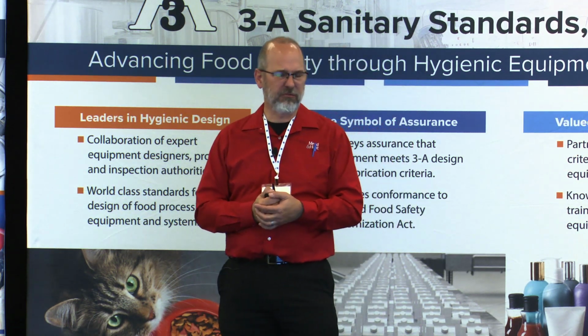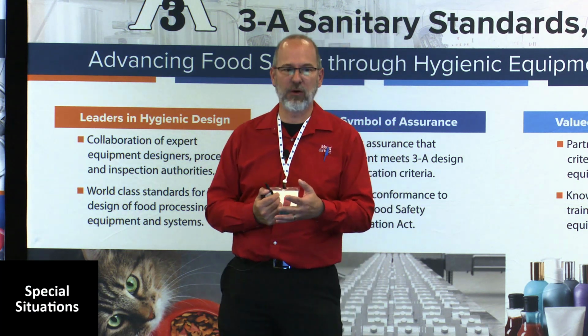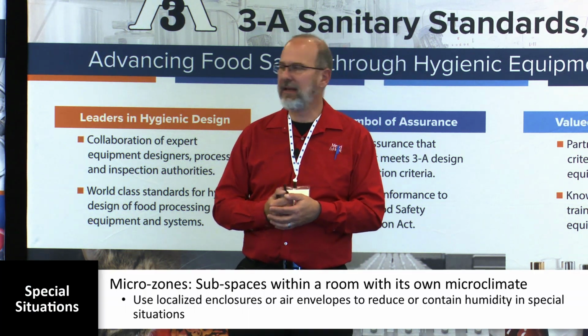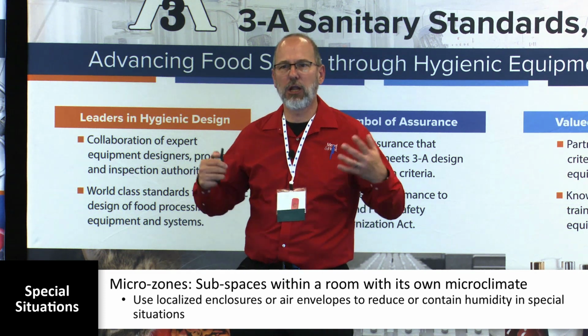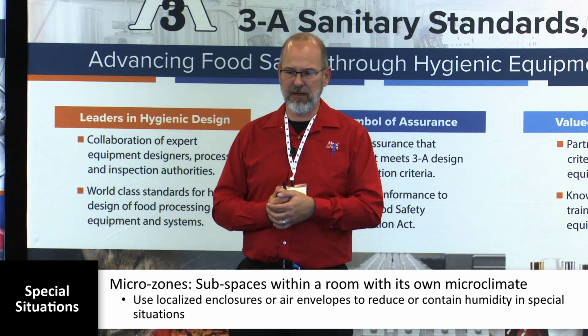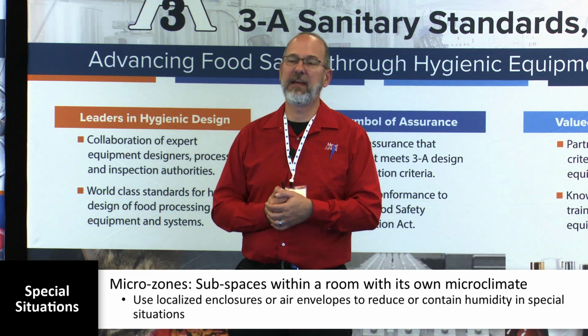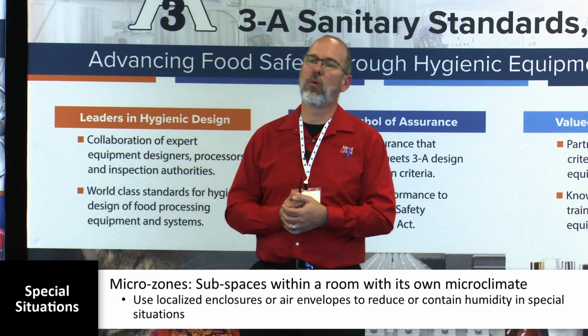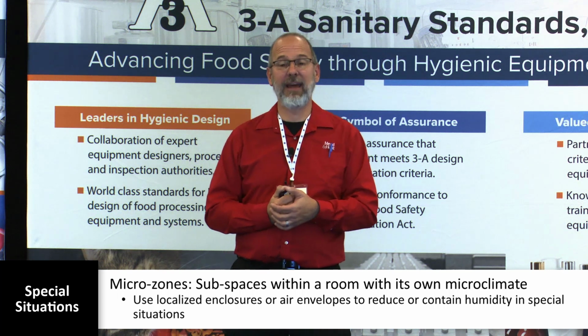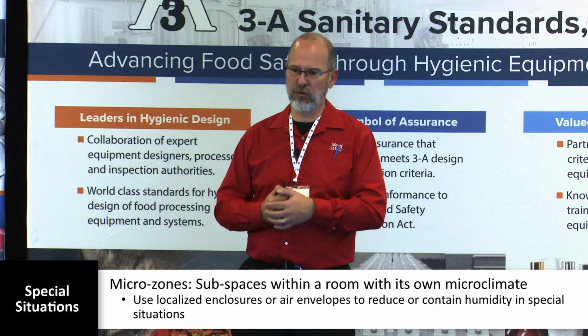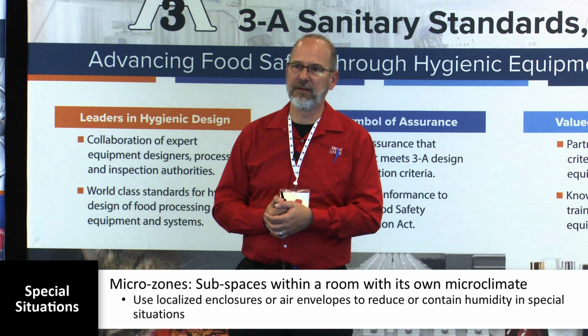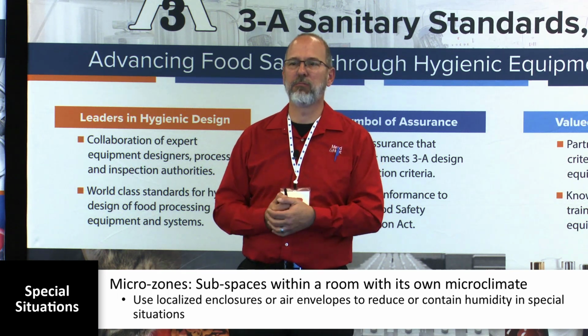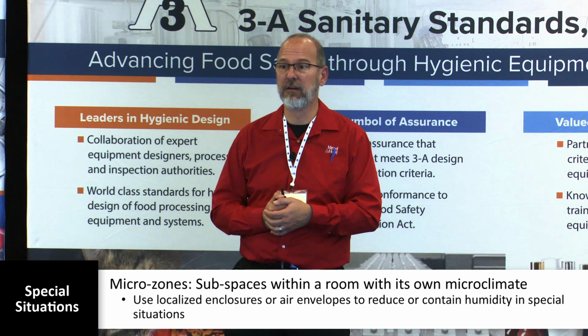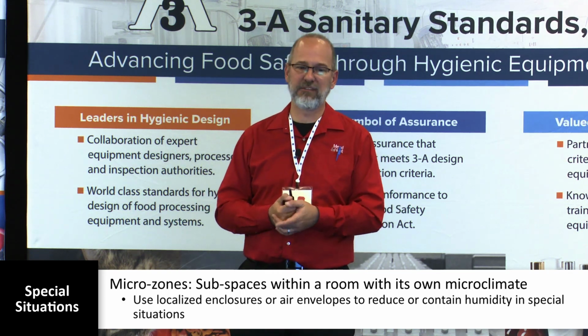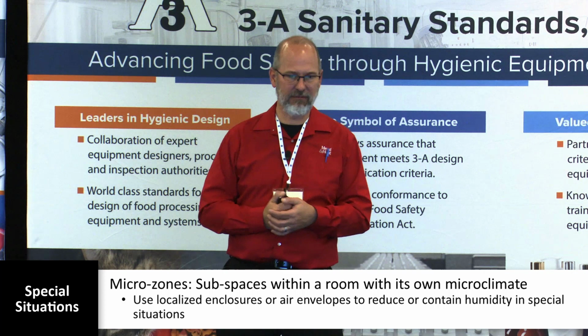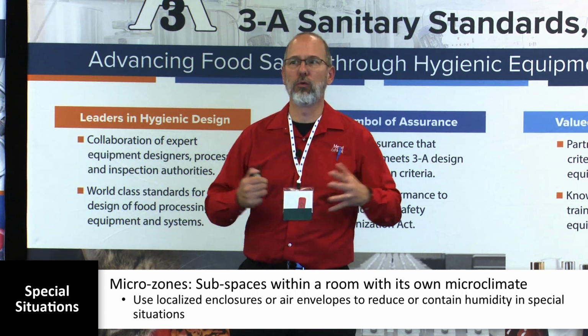There are some other special situations we run into occasionally that are just kind of worth mentioning. And Tom kind of briefly mentioned this earlier. If you've got a large process space and you've got a relatively small piece of equipment in that space that has its own special environmental requirements, if you can, you're better off trying to enclose that within its own little room or its own microclimate. And maybe that would require dedicating a small air handler just to that piece of equipment versus trying to condition the whole room to that special case. Because that can also get very expensive if you have to treat a whole room based on one piece of equipment.